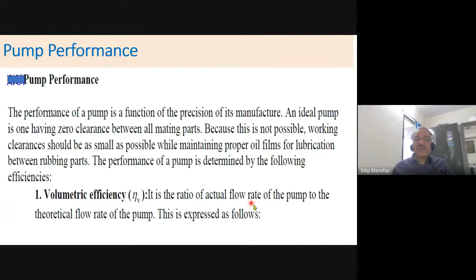Volumetric efficiency is the ratio of actual flow rate to the theoretical flow rate of the pump. It is expressed as follows: actual flow rate upon theoretical flow rate. So volumetric efficiency decides the amount of leakage that takes place within the pump due to manufacturing tolerances and flexing of the pump casing. So in the gear pump, volumetric efficiency is almost 80 to 90%. For vane pump, it is highest 92%. These are all rough figures. Piston pumps have still higher, 90 to 98%.